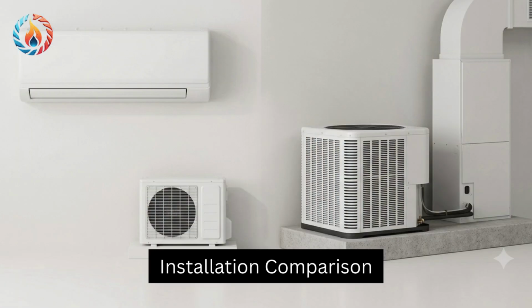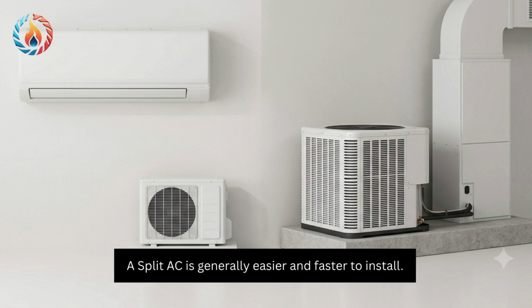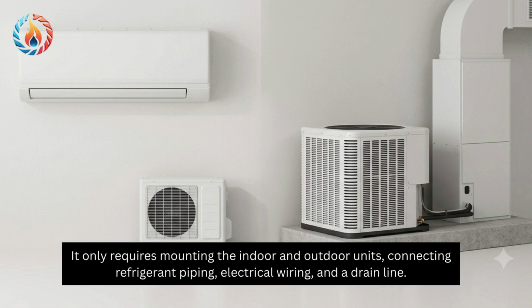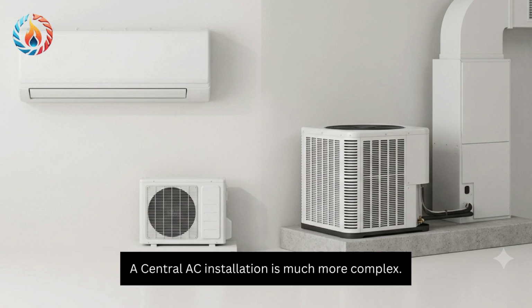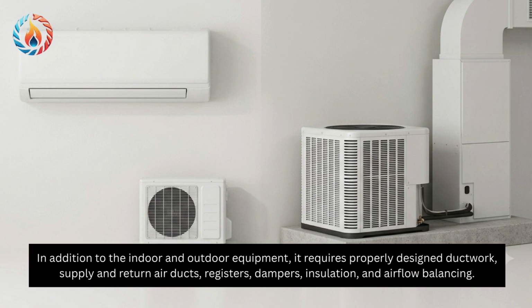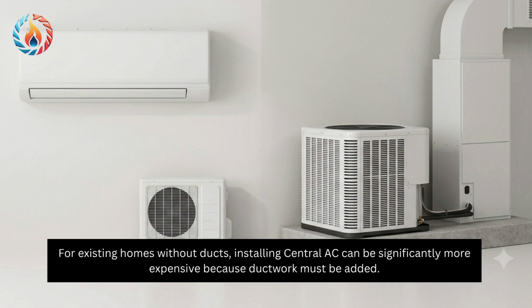Installation comparison. A split AC is generally easier and faster to install. It only requires mounting the indoor and outdoor units, connecting refrigerant piping, electrical wiring, and a drain line. A central AC installation is much more complex. In addition to the indoor and outdoor equipment, it requires properly designed ductwork, supply and return air ducts, registers, dampers, insulation, and airflow balancing. For existing homes without ducts, installing central AC can be significantly more expensive because ductwork must be added.